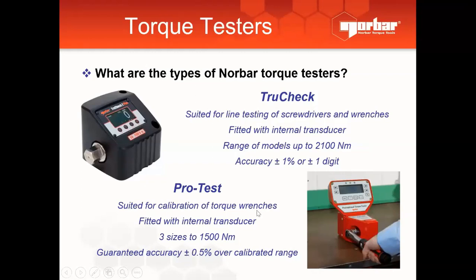Okay, additional info you have to take note. In order to check or calibrate a torque wrench under the ISO standard, it should be 4 times better in order for you to check or calibrate a torque wrench.